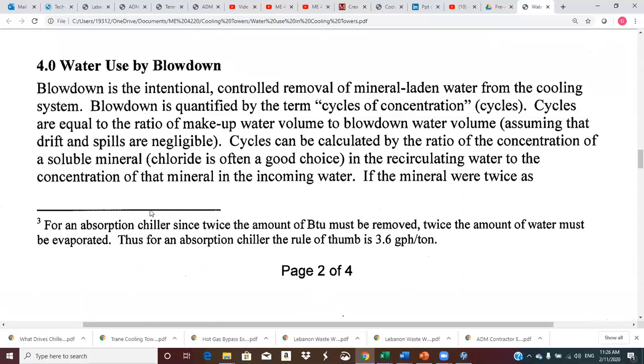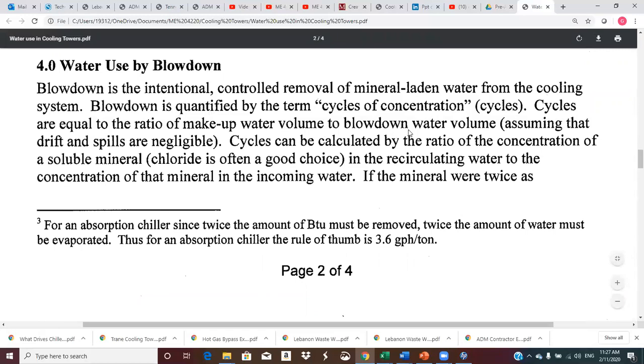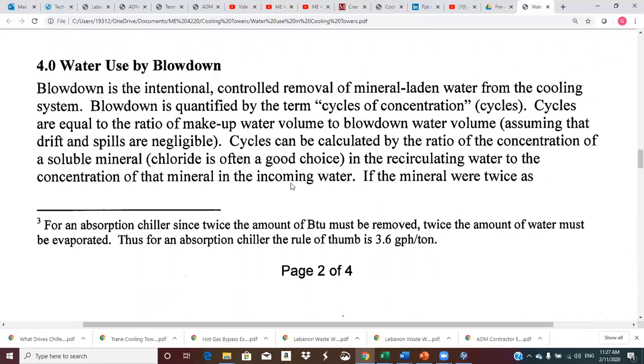Let's move on here. Item 4, water use by blowdown. And of course, we said this is the intentional draining of this mineral and bacteria-laden water from the cooling tower system. It's quantified. We use the term cycles of concentration, or sometimes just cycles. And it's equal to the ratio of the makeup water volume to the blowdown volume, assuming that spills and drifts are negligible or you've included them, whichever. Cycles can be calculated by the ratio of the concentration of a soluble mineral, chloride or some other mineral, in the recirculating water to the concentration of that mineral in the incoming water.